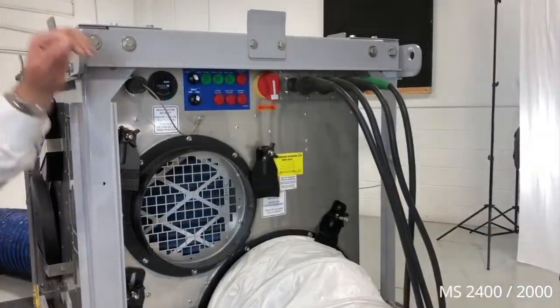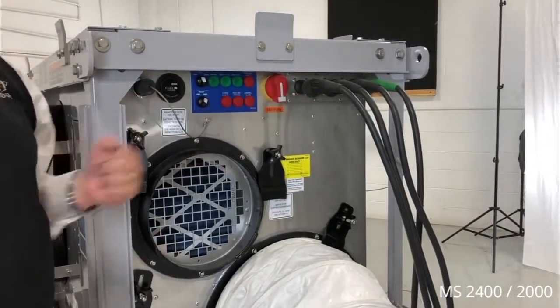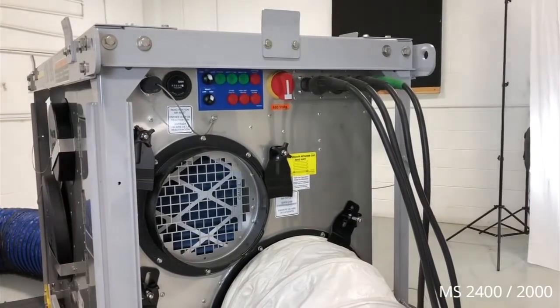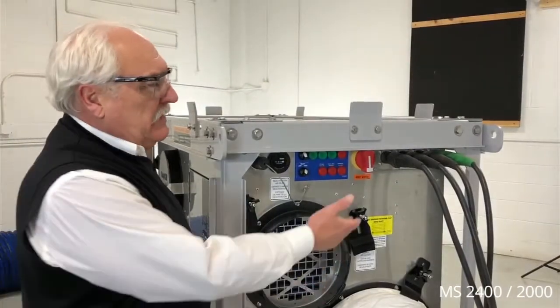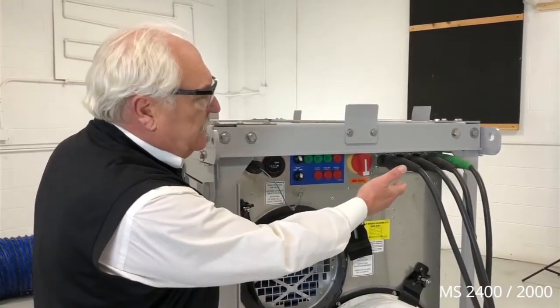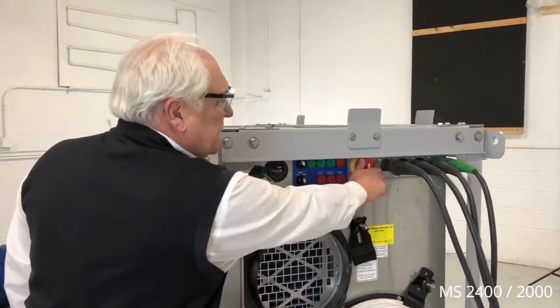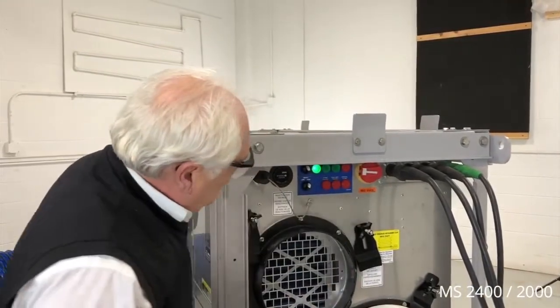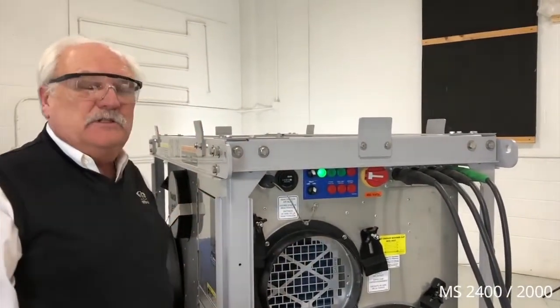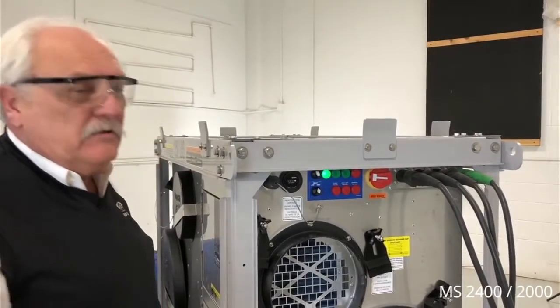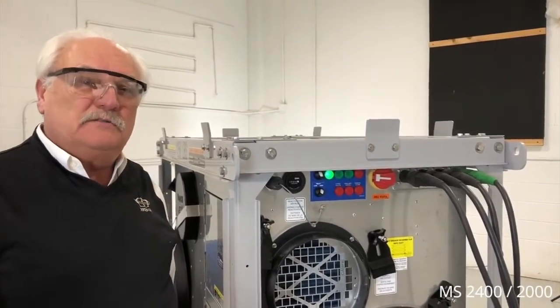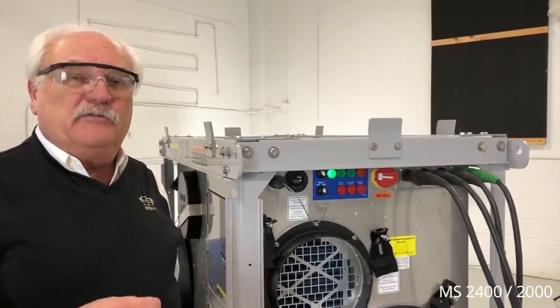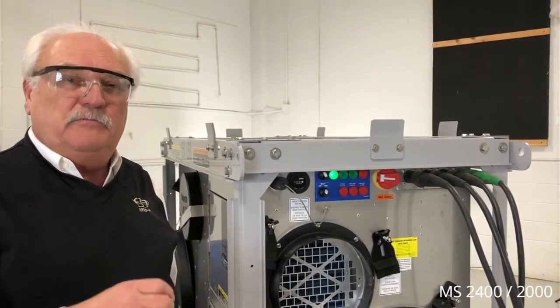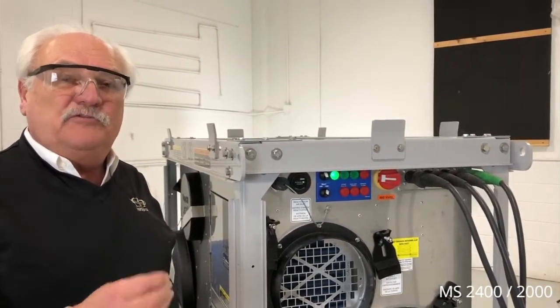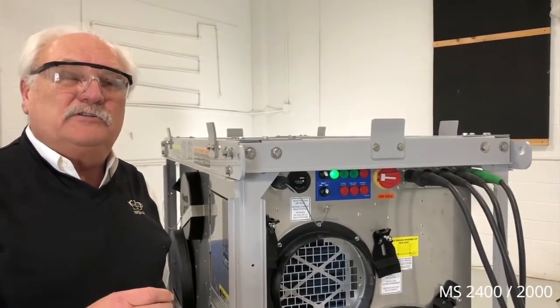With all 4 of the high voltage lines now connected, we can start the generator and begin the startup of the system. With the main power now connected with 480 volt 3-phase, we can turn the main disconnect to on. This will initiate a green light that shows that the power is on to the unit, and it'll start warming up the microprocessor. You should anticipate a delay of 30 seconds to 1 minute until the microprocessor does its self-check and then allows the unit to start sequencing.